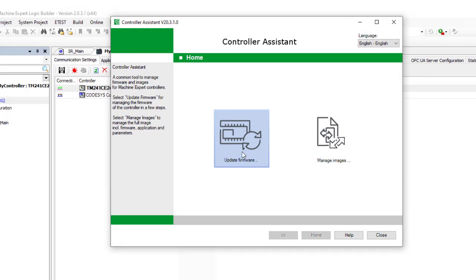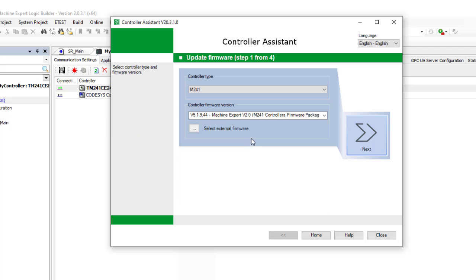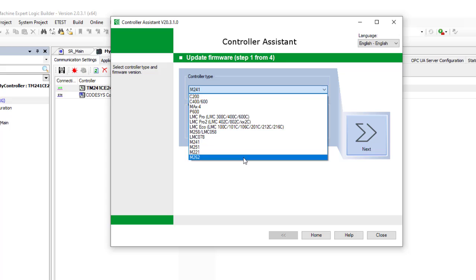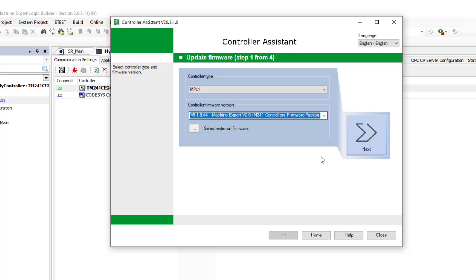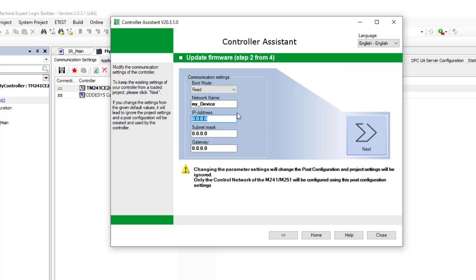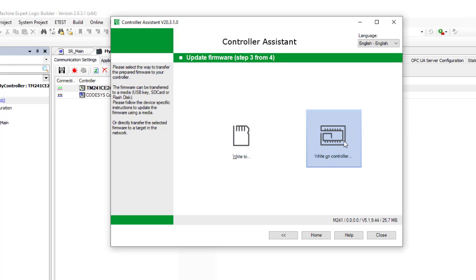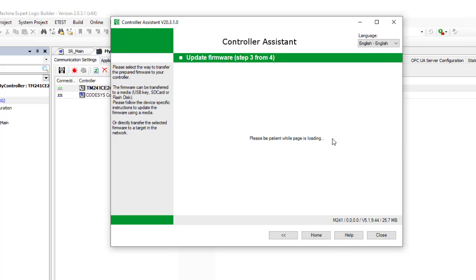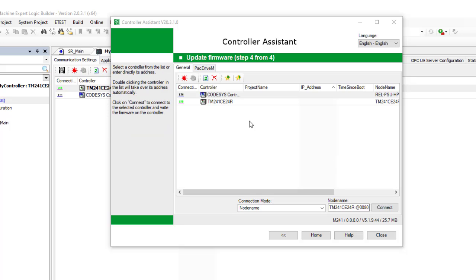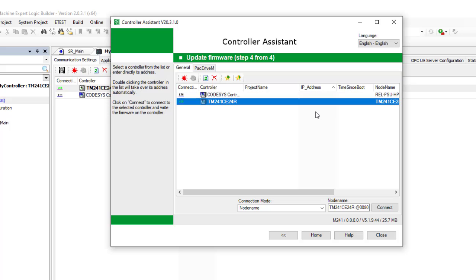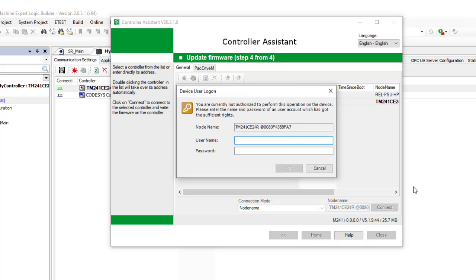In Controller Assistant, we have two options: 'Update Firmware' or 'Manage Images.' We choose 'Update Firmware.' We select the version of the logic controller we have, which is M241, then choose the firmware version — we only have one available here. We keep the other options as default and press Next. Here we have two options: 'Write to a Flash Disk' or 'Write to the Controller.' We choose 'Write to the Controller,' select our controller TM241CE24R by double-clicking, keep other options unchanged, and press Connect.